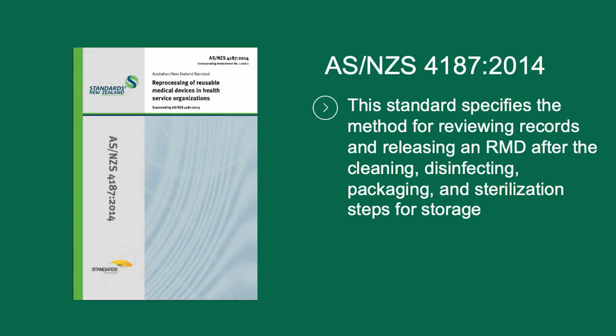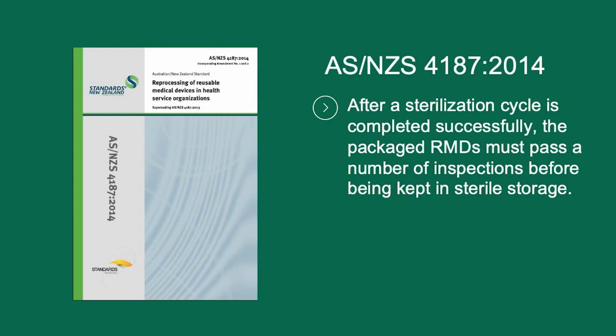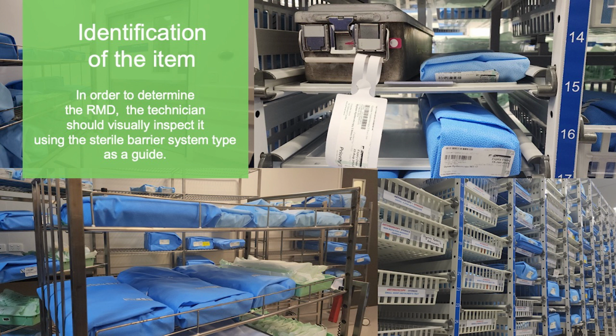This standard specifies the method for reviewing records and releasing an RMD after the cleaning, disinfecting, packaging, and sterilization steps. Identification of the item. To enable the sterilization of an RMD or RMDs, packaging is placed around them using a sterile barrier system (SBS), stopping microorganisms from entering a sterile RMD and enabling aseptic presentation of the RMD at the site of use. An SBS plays a crucial part in maintaining patient safety.